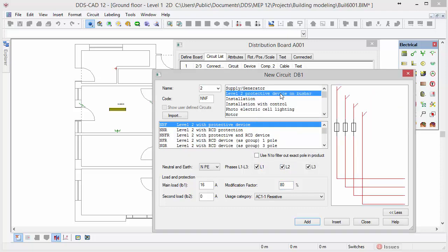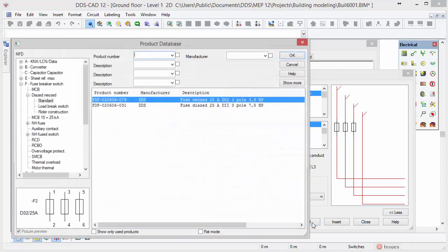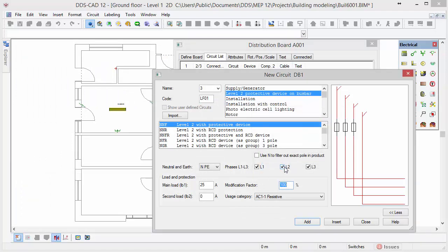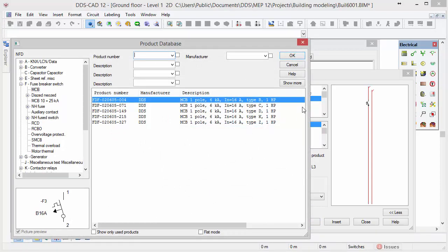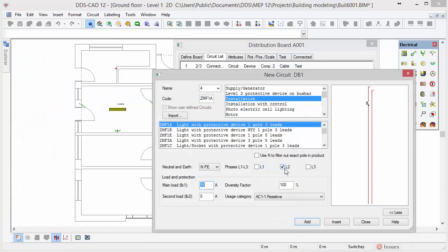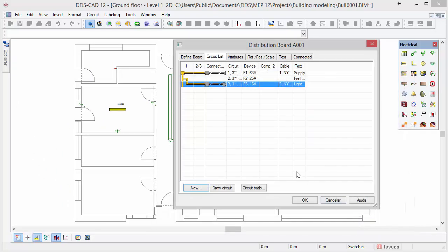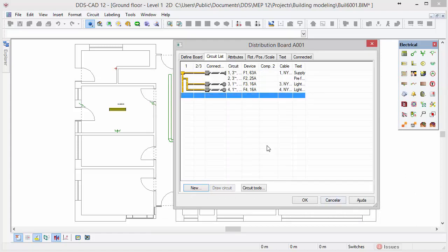Next select the category level 2 protective device on busbar and the first subcategory. You can change the load to 25 amperes and the modification factor to 100% and click add. Again DDS-CAD suggests a fuse. Click OK, give a name to the circuit and click OK once more. At last we will define a circuit for the lighting. Select the category installation and the first subcategory below. Change the load to 16 amperes and click add. Select an appropriate MCB fuse breaker and click OK. Give a name to the circuit and click OK, then click close to view the circuit list. The light circuit can be easily copied by using the shortcuts Ctrl-C, Ctrl-V. Switch to the tab define board to insert the distribution board in the model.